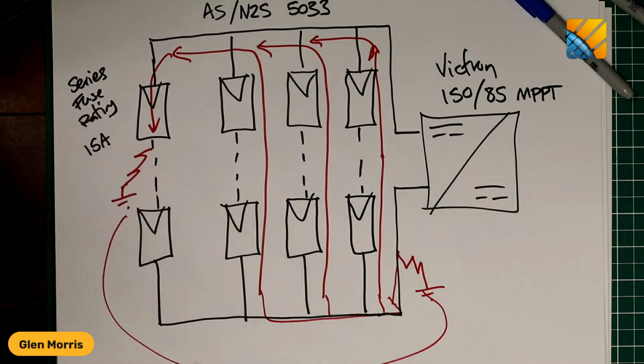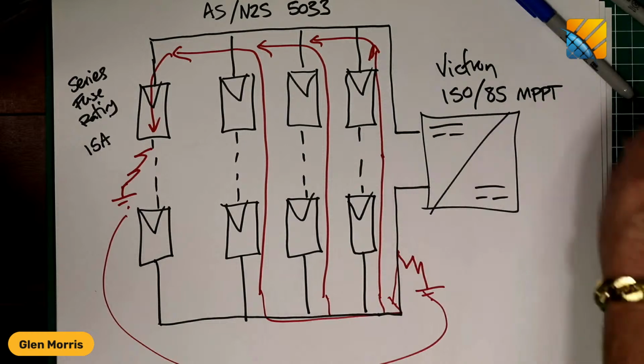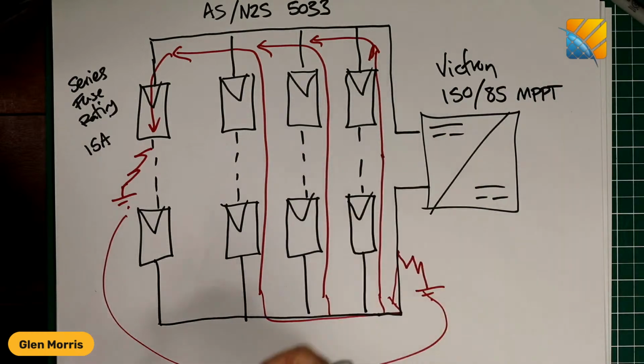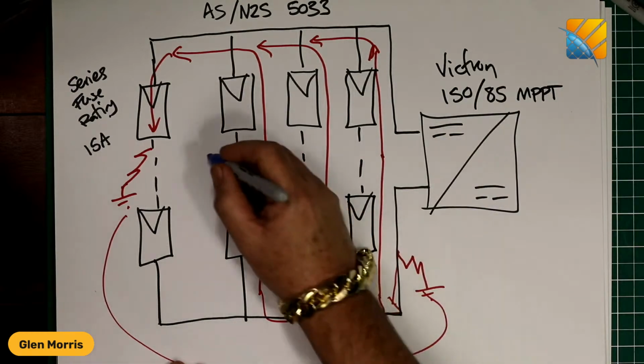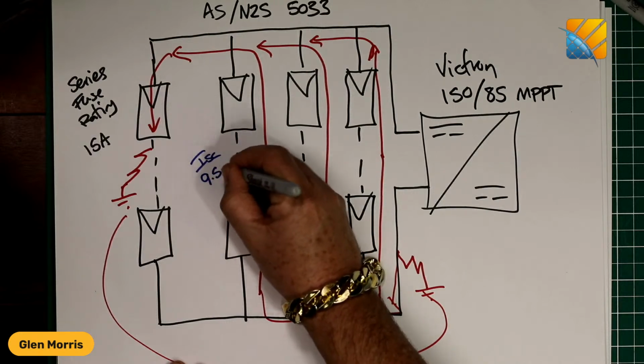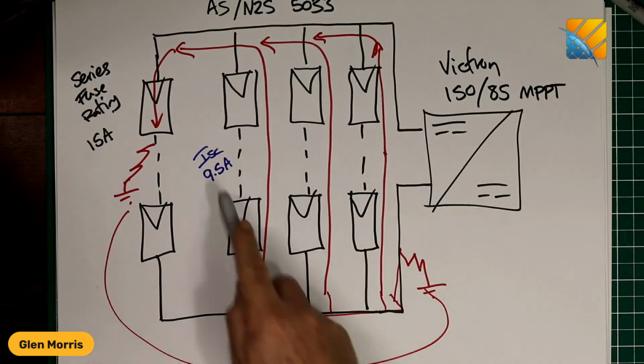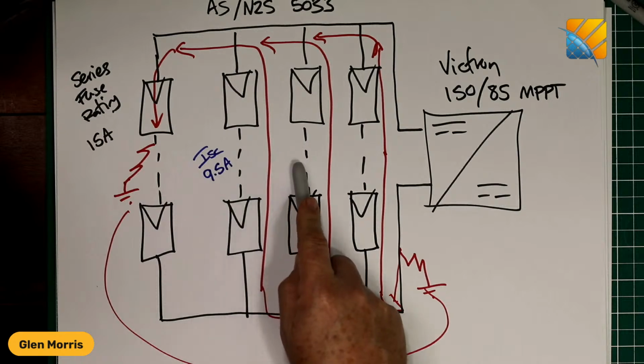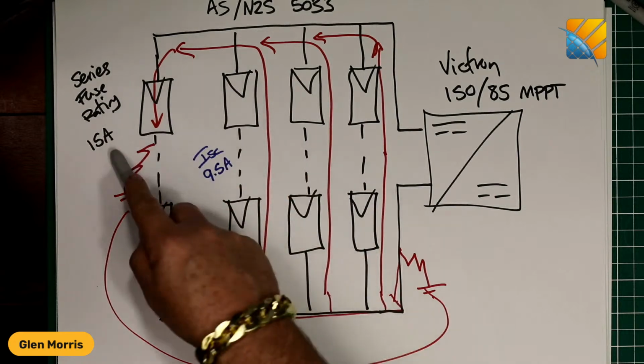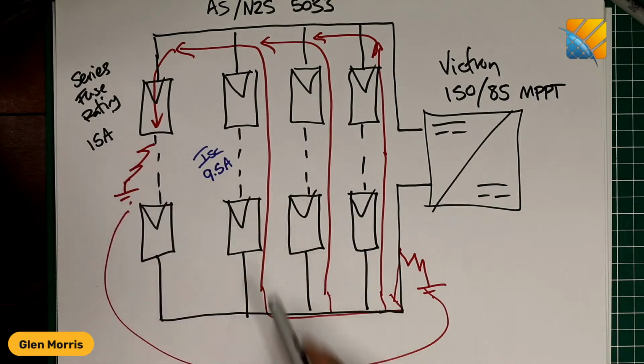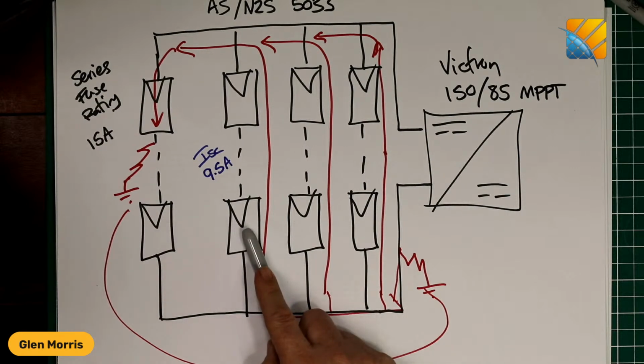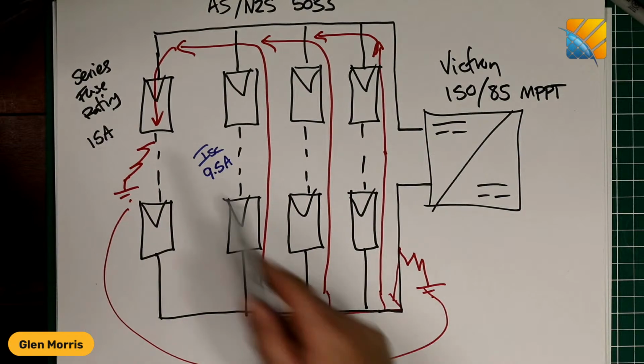So that fault condition would mean that the short circuit current of 3 strings is flowing in reverse. Now, if it exceeds that number, you need fusing on all strings on both poles. So it's all about knowing what the short circuit current of the module is. Let's write that in here. The short circuit current is 9.5 amps, and 9.5 plus 9.5 is 19 amps. Straight away, we've exceeded that, so you'd need string fusing. So once you went beyond 2 parallel strings in this configuration, string fusing would kick in. But it all depends on that number there.